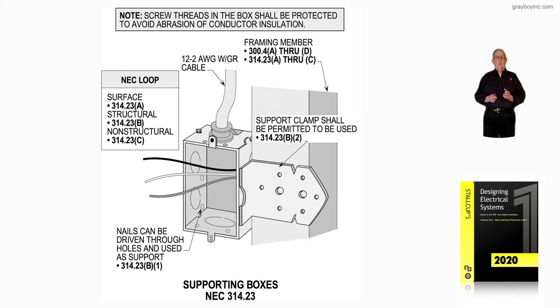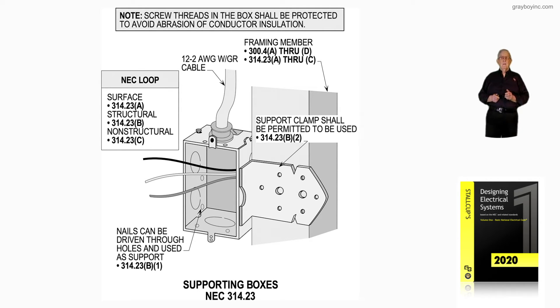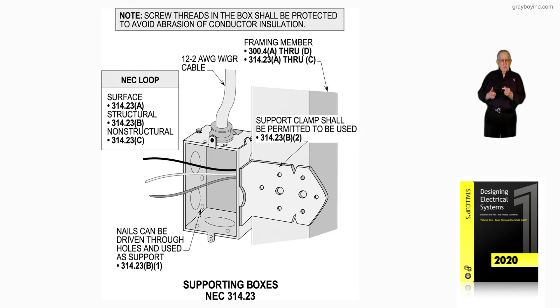Notice the note — it talks about screw threads in the box shall be protected to avoid abrasion of conductor insulation. This is where you might take a 16-penny nail and drive it through the back of the box. If that is the case, to support it to a wooden stud, it would sit back at the back of the box so that the insulation would not be damaged.